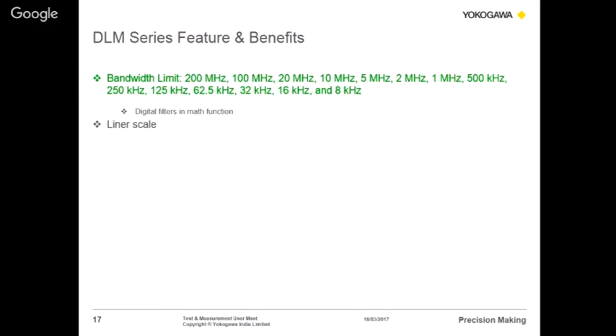Even though you have a 200 megahertz oscilloscope, the bandwidth limit can be brought down to 20 megahertz. But if you want to analyze a 1 kilohertz or 2 kilohertz or 5 kilohertz signal, at 20 megahertz bandwidth the depth of analysis or sampling points is not great enough to capture complete information of the kilohertz signal. So the main function is our bandwidth limit - the only company which provides the lowest bandwidth on the lower side is up to 8 kilohertz. You can limit the oscilloscope bandwidth as low as 8 kilohertz, from 200 megahertz down to 8 kilohertz. That is a key parameter when working in power electronics.